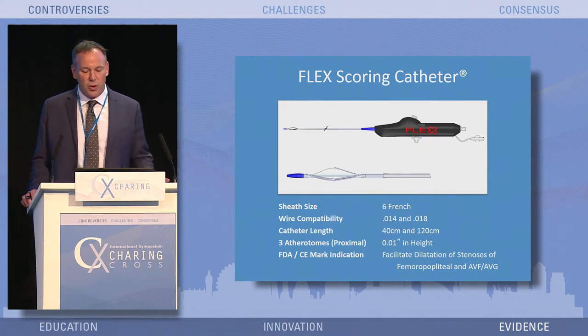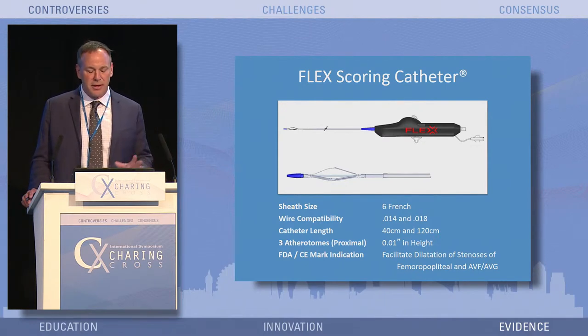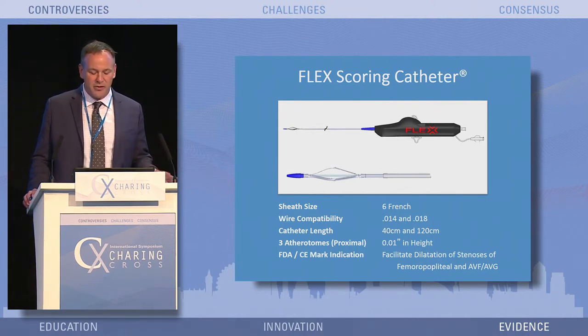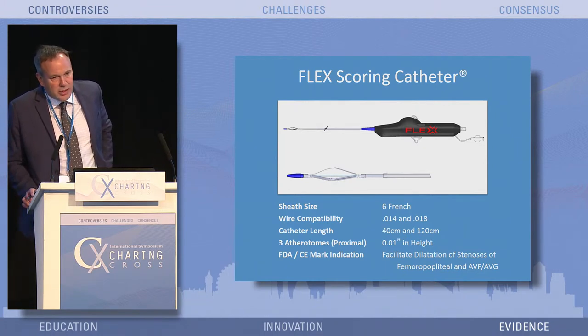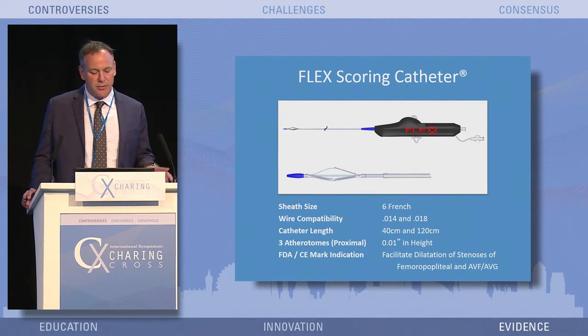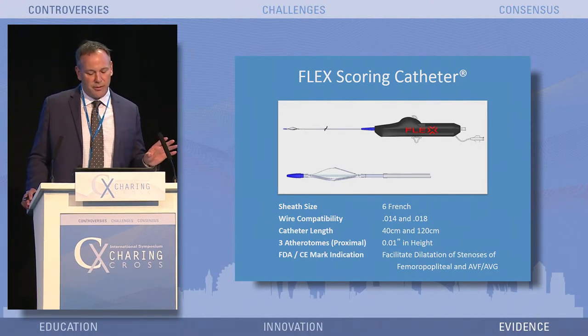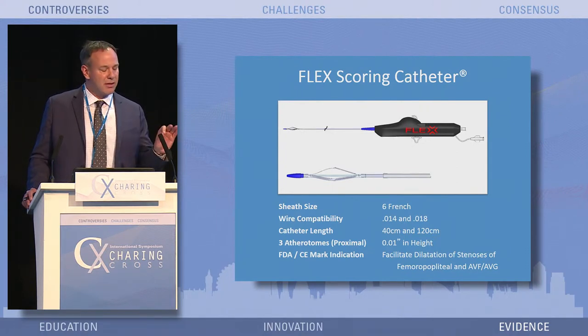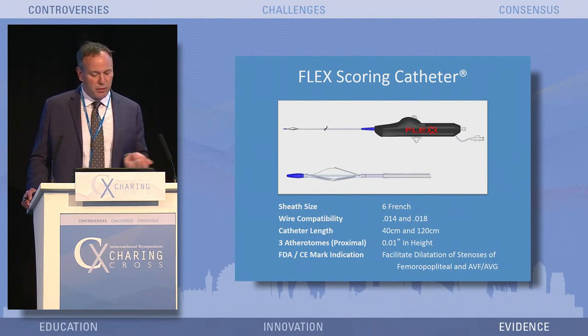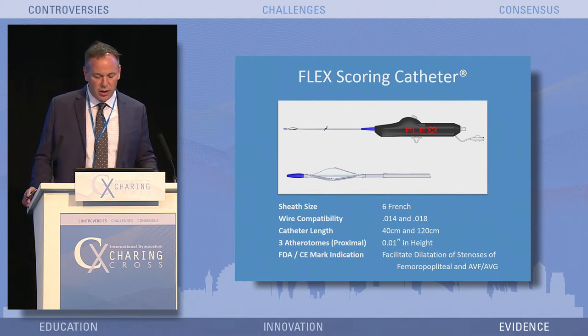This is the actual flex-scoring catheter. The difference between this and other scoring technologies on a balloon is those are more forced dilatations, whereas this is done under about one atmosphere of pressure. It's 6 French compatible, goes over a 014 and 018 wire. Catheter lengths are 40 centimeters and 120 centimeters, with indication for both the femoral popliteal segment and for AV grafts. You can see the atherotomes there. It's a retrograde cutting — all scoring elements are on the back surface. You pass the lesion, open it up, and pull backwards. With three atherotomes, you can go back in, rotate 30 degrees, pull it back, rotate another 30 degrees — no balloon exchanges — and get up to nine cuts.